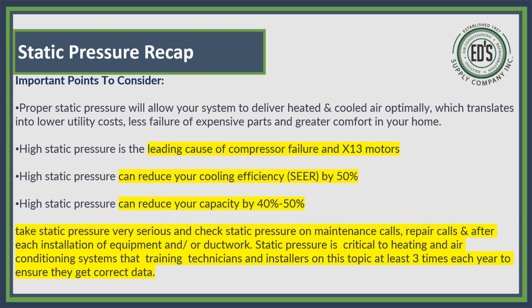Now you could speed the fan up. At that point, you would have to put a bigger return. So they had 14-inch flex, and it was kinked up pretty bad. So they had to go in and put 16-inch flex in, get the kinks out of it, pull it tight, stretch it as tight as they could, refasten it, and then recheck your static pressure. Every time you make an adjustment, you got to check static pressure. So just because you take 14 off and put 16 on and walk away doesn't mean you're right. You may have to adjust your fan speed at that point. So you got to look at that and see.